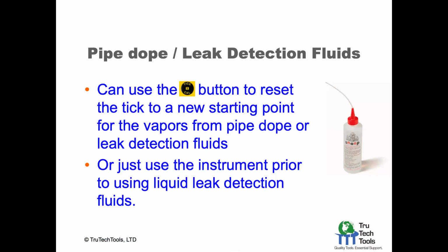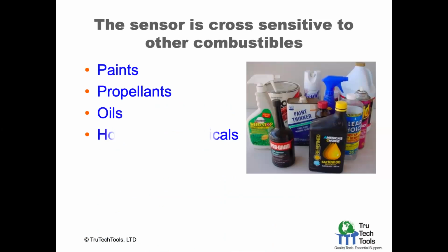And that's in fact what a lot of people do. They'll get it real close, to the general vicinity, with the leak detector. And if it isn't obvious, then hit it with some leak detection fluid, which we also sell at TruTech, but you can get it pretty much anywhere, to then see the bubbles and know that at that point you're leaking fuel from the pipe.